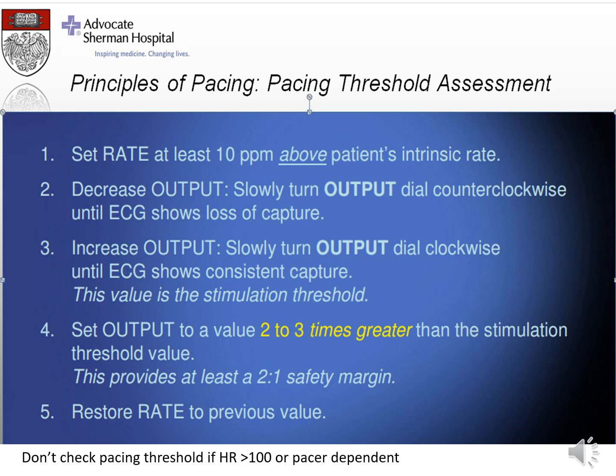Then what you're going to do is put your pacer settings back to where they were. What you want to do is make sure you have your output, or your mA, at a safe level. I've heard different things. I've heard 1.5 to 2.5. I've heard 2 to 3 times the amount of the stimulation threshold, just so you have a little bit of backup in case you suddenly need your patient's pacemaker in a hurry.